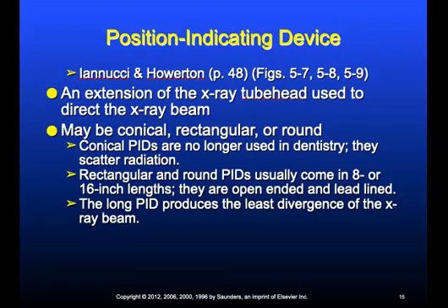For infection control purposes, the PID, along with the tube head, should always be covered with a plastic barrier and changed in between each patient. The end of the PID should be positioned close to the extraoral portion of the film holder and lined up correctly in all 3 planes to make sure that you have an accurate exposure and image production on the film.